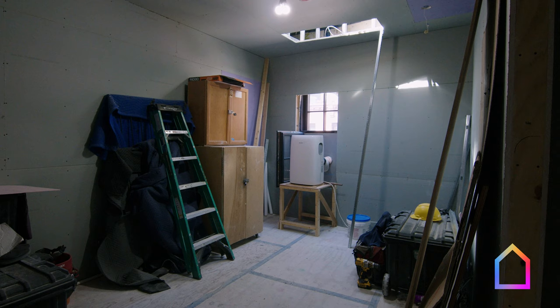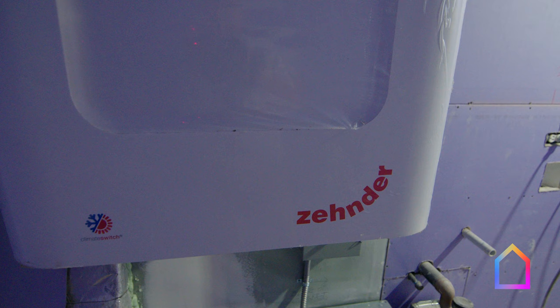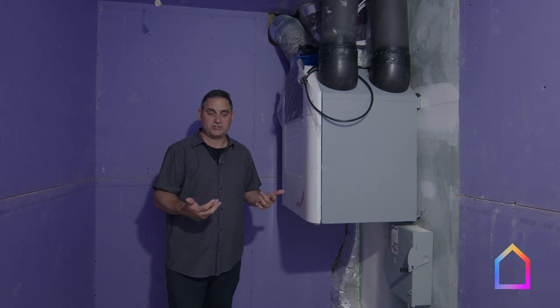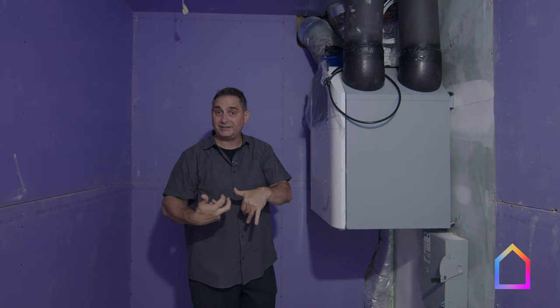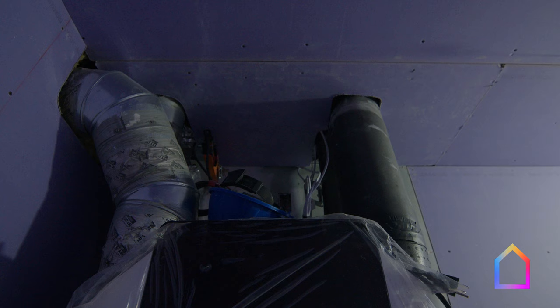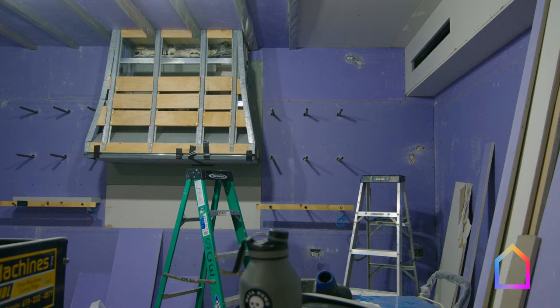Walking past the bedroom and into what will be a laundry room — I'll have my washer, my dryer, some nice cabinets that cover the mechanical. This is what I said was an ERV, or energy recovery ventilator. Why call it that versus just a fresh air system? Because a fresh air system just dumps all the conditioned air from the house and brings in new air from outside. Imagine doing that when the air is 20 degrees outside. You want the air from inside and the air from outside to pass by each other but still be filtered, so you're bringing in relatively conditioned air. These constantly supply all living spaces with filtered fresh air and constantly exhaust from bathrooms, kitchens, and laundry rooms — creating really healthy houses. When you need more exhaust, you press boost and get even more filtered fresh air.